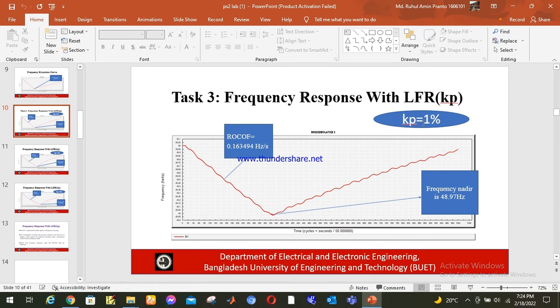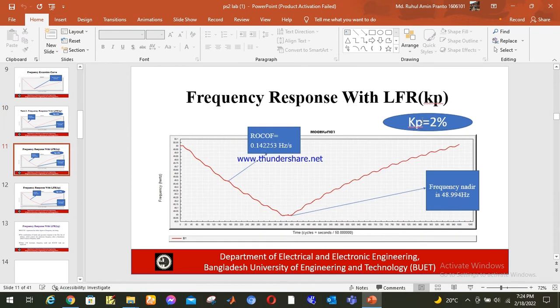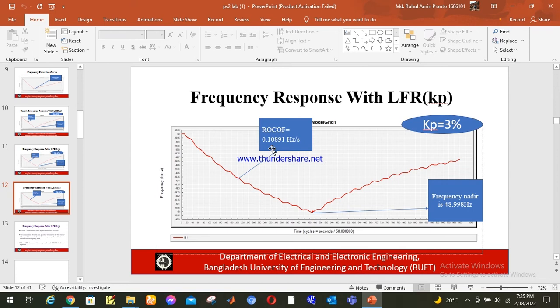When kp is 1%, RoCoF is 0.163494 Hz/s and frequency nadir is 48.97 Hz. When kp is 2%, RoCoF is 0.142253 Hz/s and frequency nadir is 48.994 Hz. When kp is 3%, RoCoF is 0.10891 Hz/s and frequency nadir is 48.998 Hz. We can clearly see that as kp increases, the frequency nadir increases and RoCoF decreases — meaning both RoCoF and frequency nadir are improved with higher kp values.